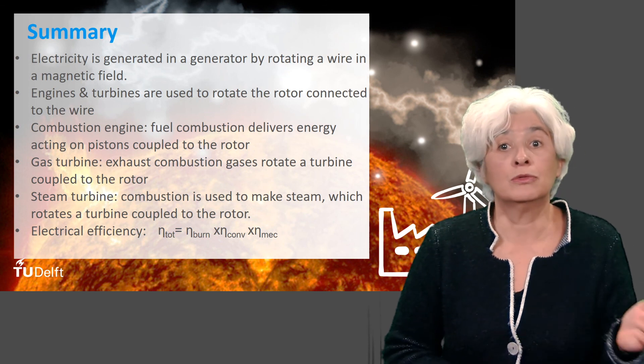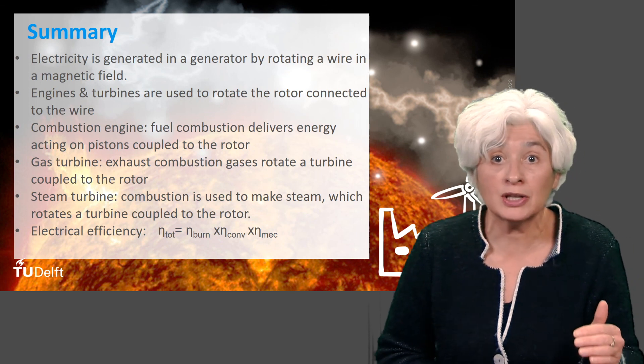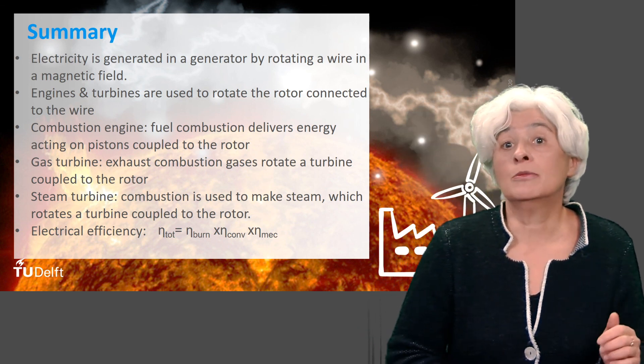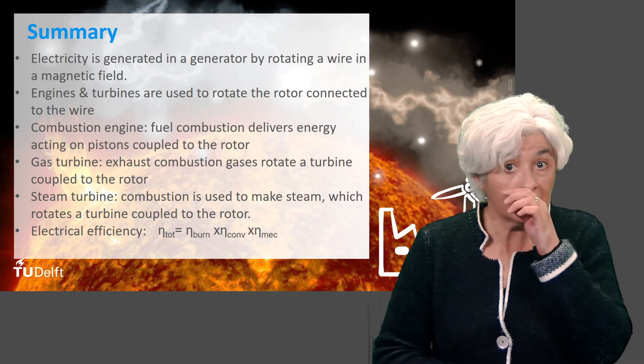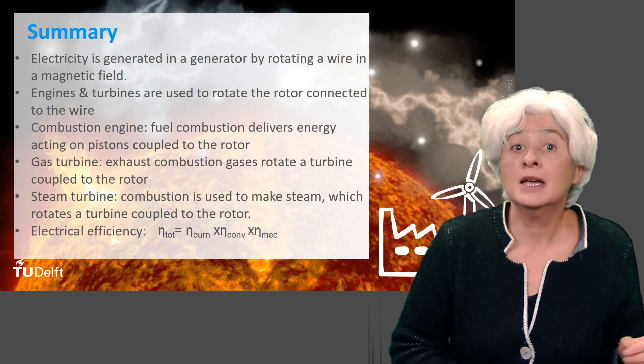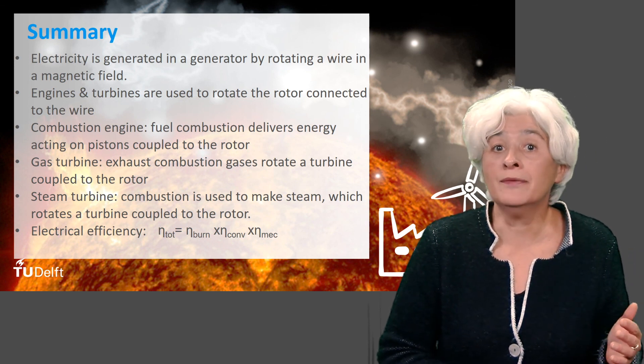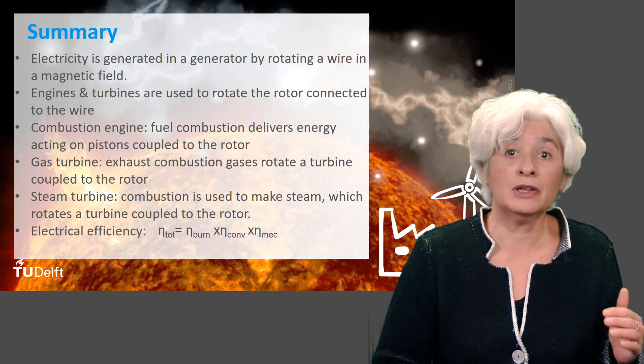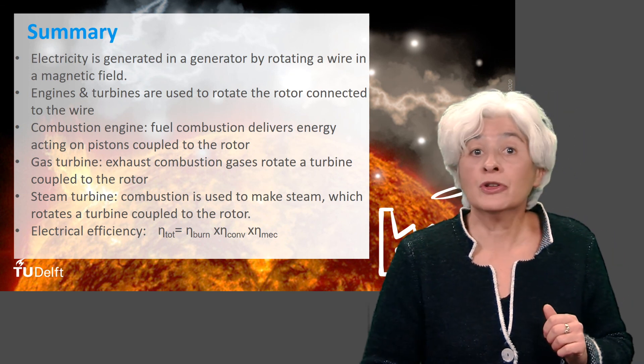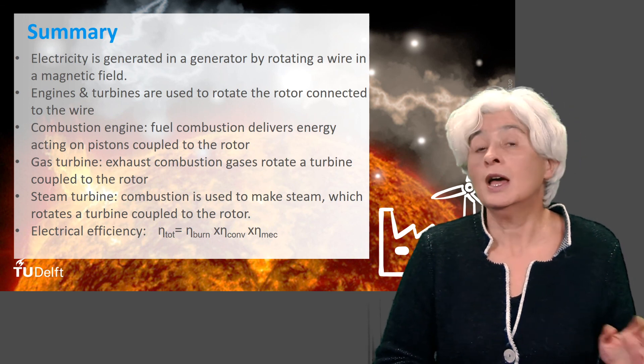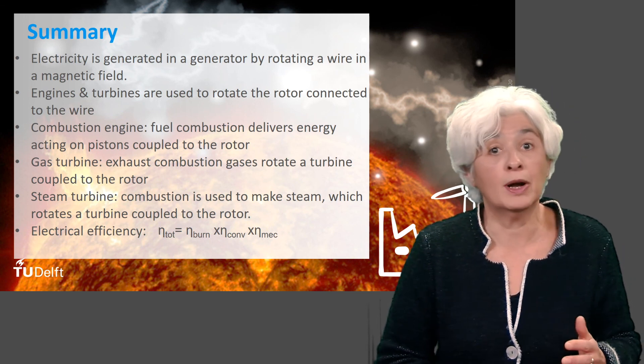The conversion from heat to rotor rotation is much less efficient, being around 0.5. There is a theoretical maximum to this conversion efficiency depending on the temperature levels. And then, there are the mechanical losses, the most important ones taking place in the generator itself. In total, the efficiency of such systems is between 0.25 for the poor ones and 0.45 for the good ones.